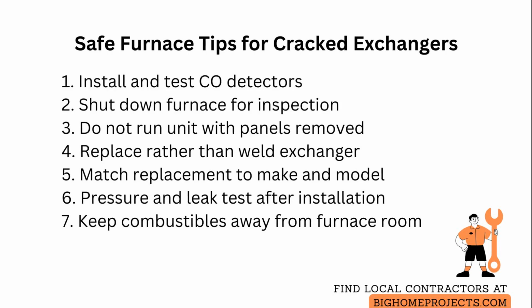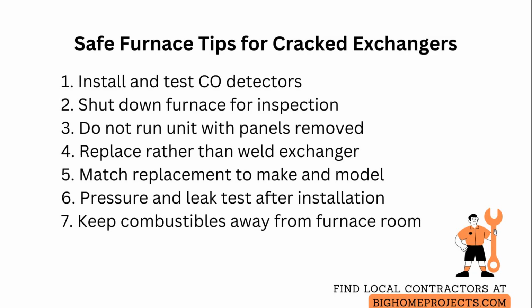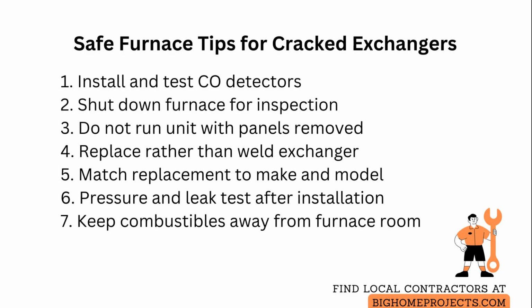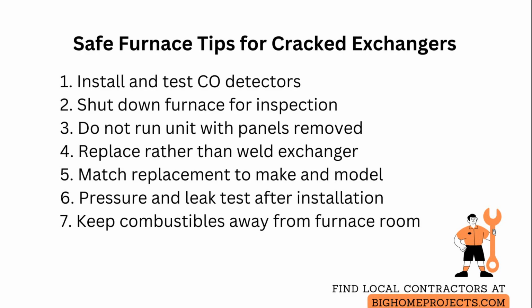Replacing a cracked heat exchanger is often the only durable fix because welding or patching on modern units is unreliable and can void warranties. So get a replacement matched to the make and model and have a qualified technician perform the swap and pressure and leak testing afterward.